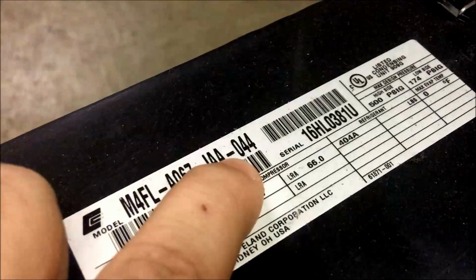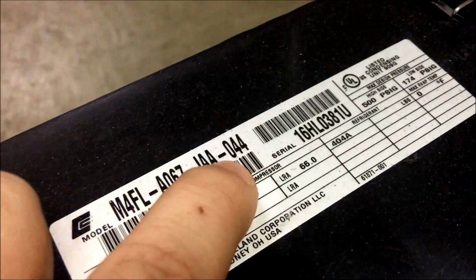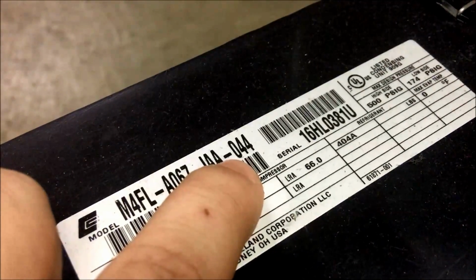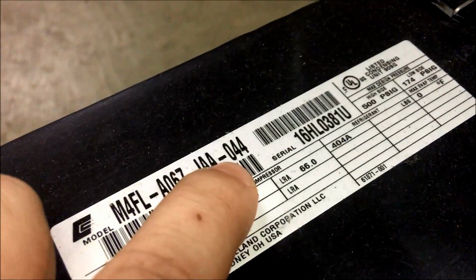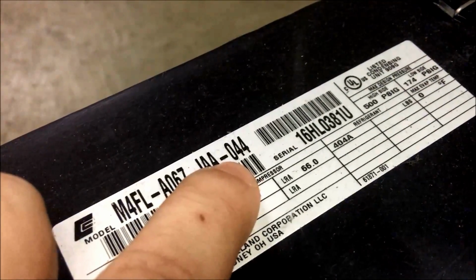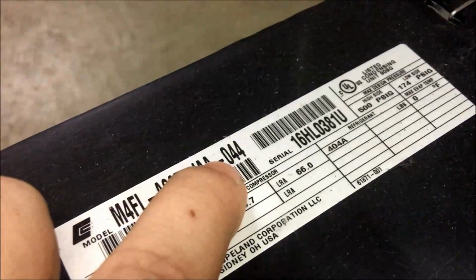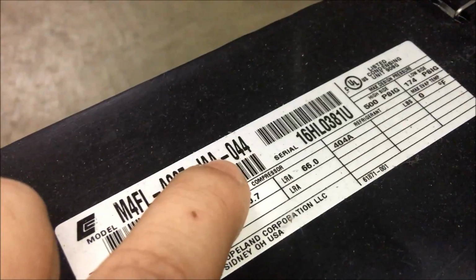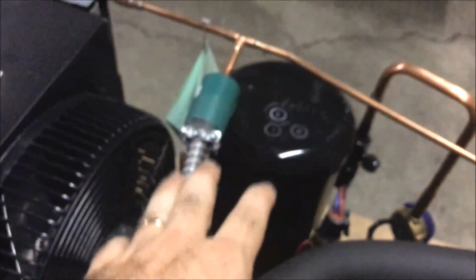And that's going to tell you whether the unit is UL listed or if it's a UL recognized unit, or if there's no UL listing at all. In this case, it's a 0. That means it's a UL listed unit. So that means it's got the fan guard and the conduit, and it's got pressure controls and all these other UL safety devices on it. So it has all those regulations for it.